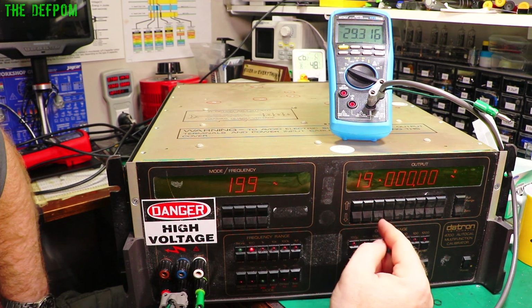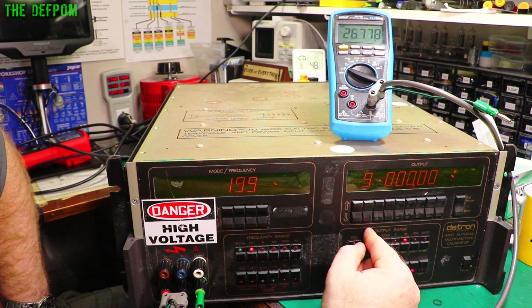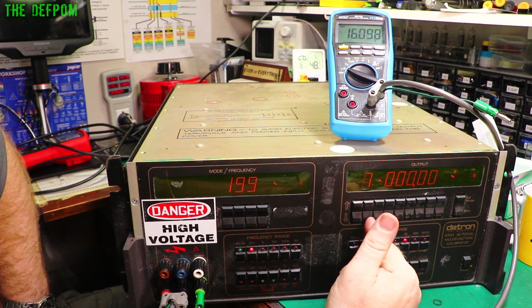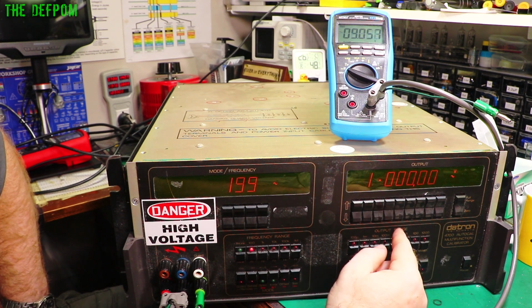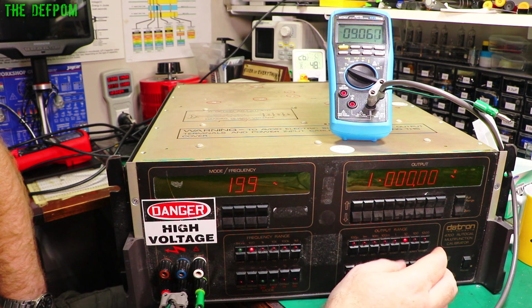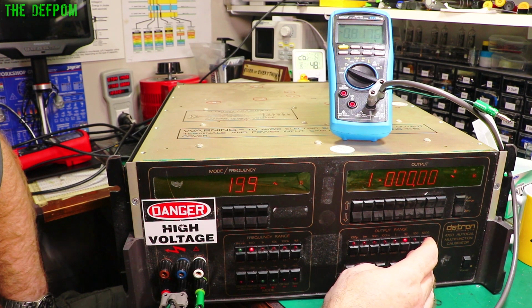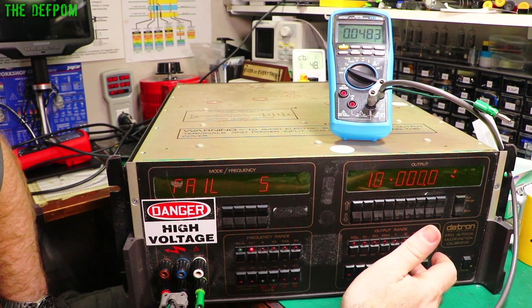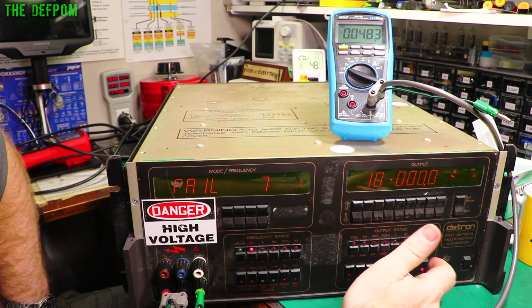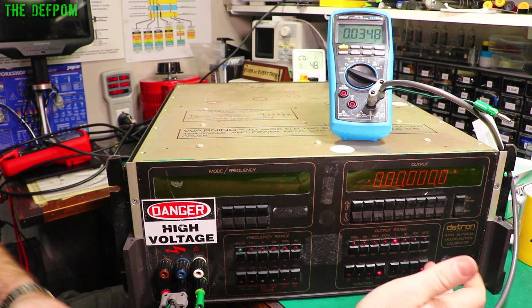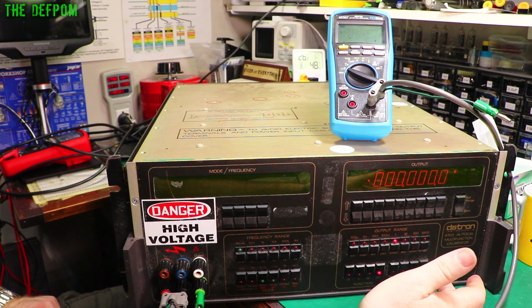And I'm getting 29, it's out by 10. At 9 I'm getting 16. So at the 1 I'm getting 9. So there's definitely something going on there. Let's try 100 volts. Fail 5. We've got an error message, that's something. Can I turn it back on? No. Reset. Fail 7. Fail 5 and fail 7. Can I turn it on?